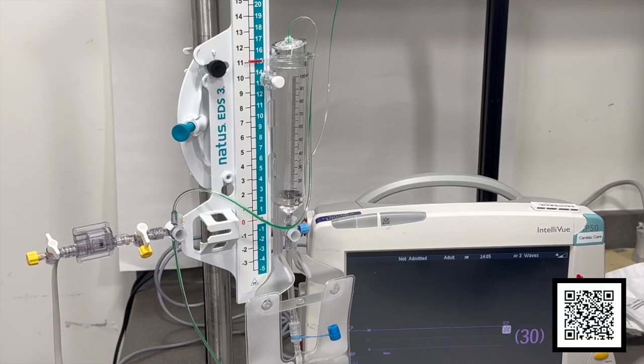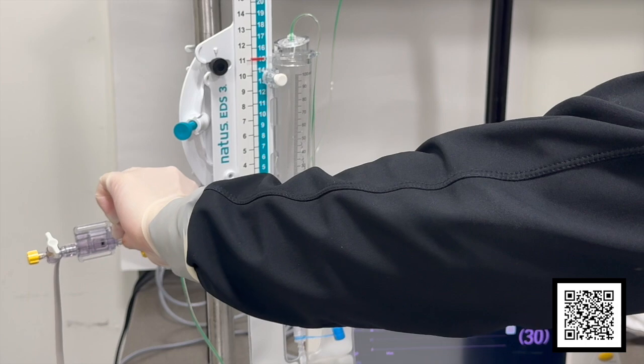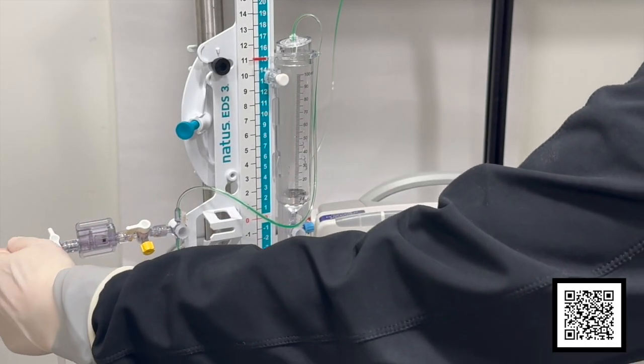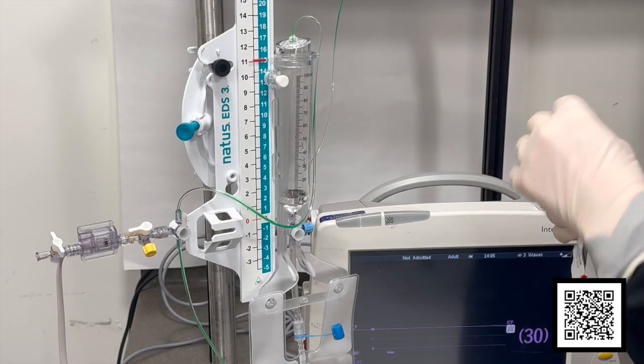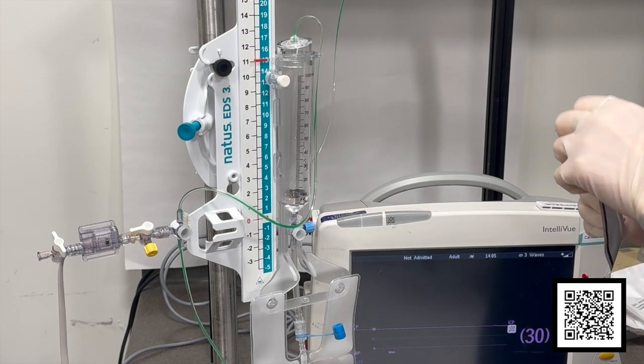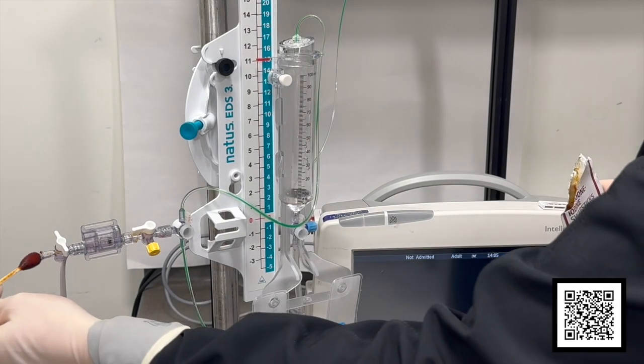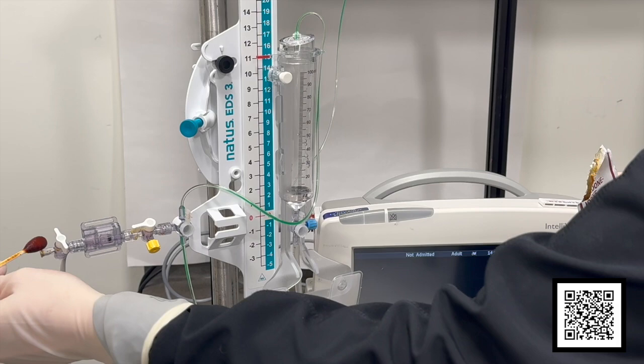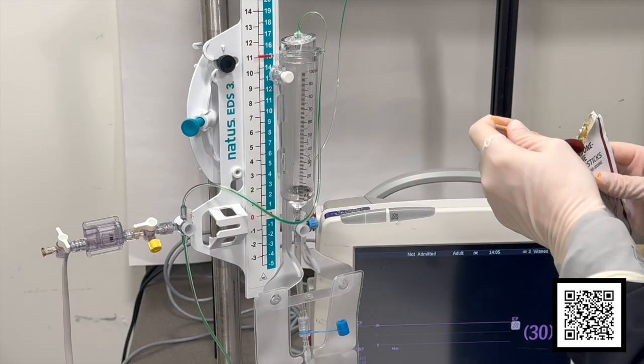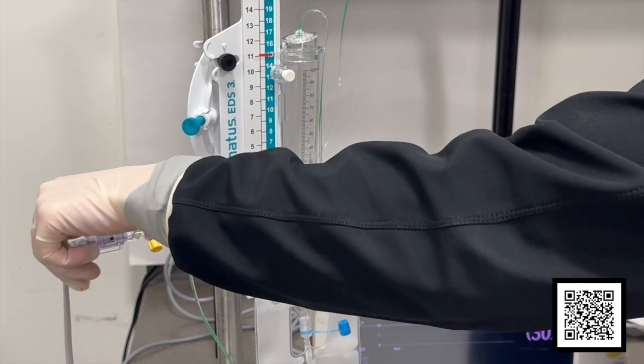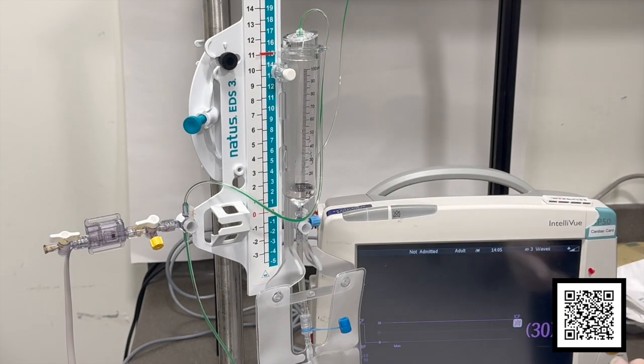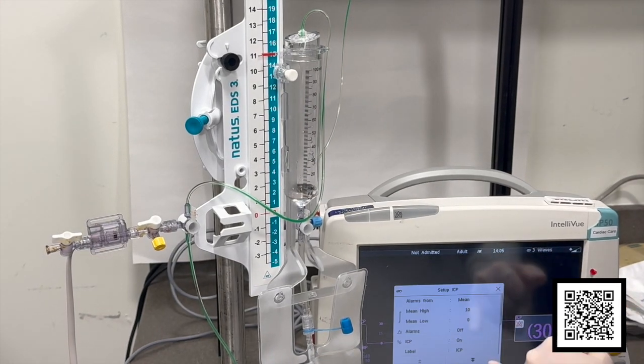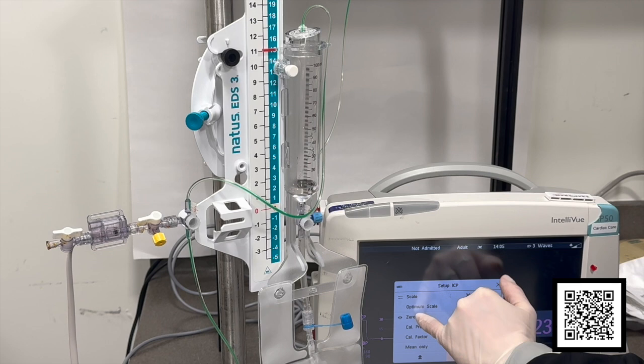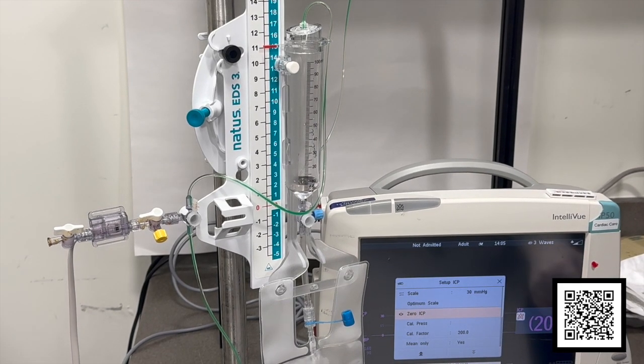In the second method, you turn the stopcock off to transducer position and open the far end cap to air. Then the valve can be swabbed with betadine and the far stopcock open to air. Following, the clinician will zero the bedside monitor, return the valve off to air, and replace the sterile cap.